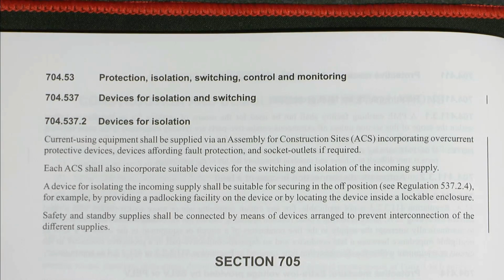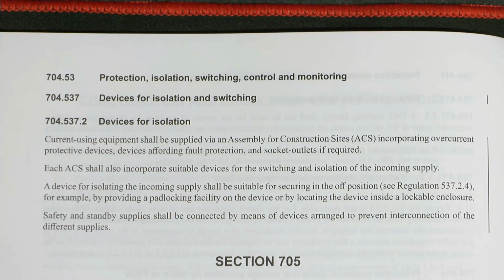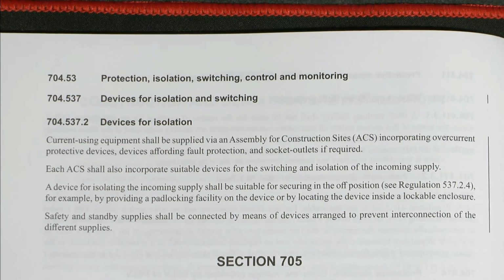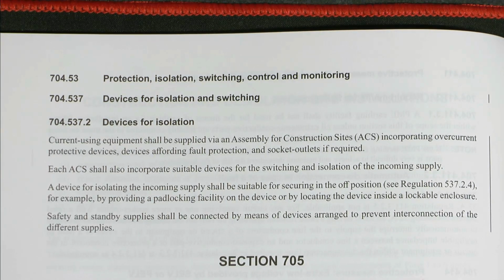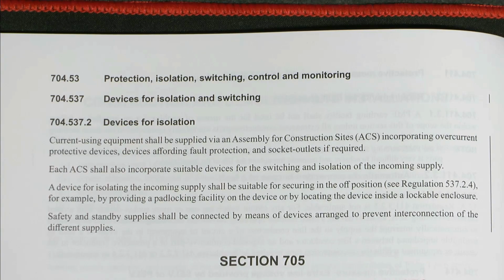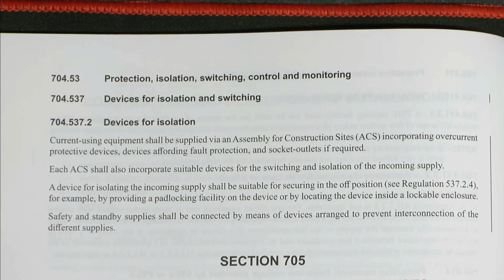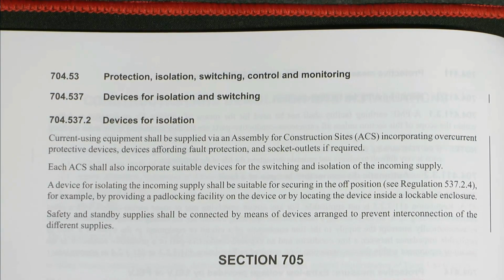And this is another one which has been expanded somewhat. Devices for isolation. Again, previously this was just a single sentence, which was essentially the third one there, where it starts a device for isolating the incoming supply. So now we've got current using equipment shall be supplied via an assembly for construction sites or ACS, incorporating overcurrent protective devices, devices affording fault protection and socket outlets if required. Each ACS shall also incorporate suitable devices for the switching and isolation of the incoming supply.